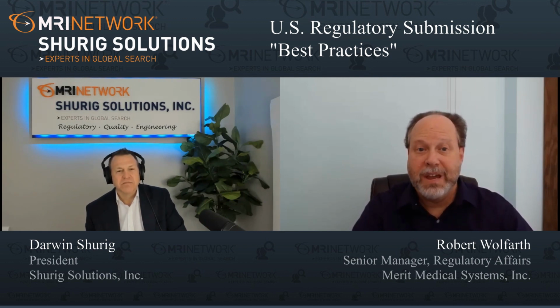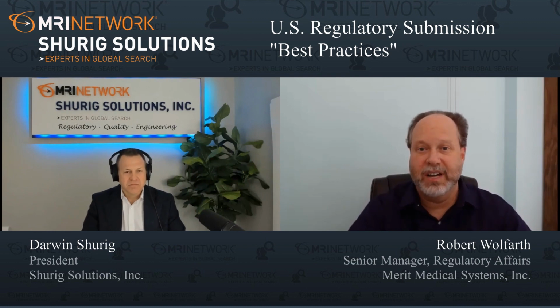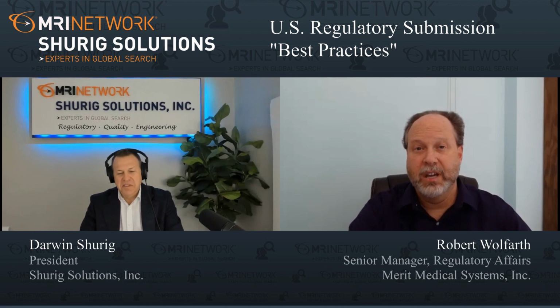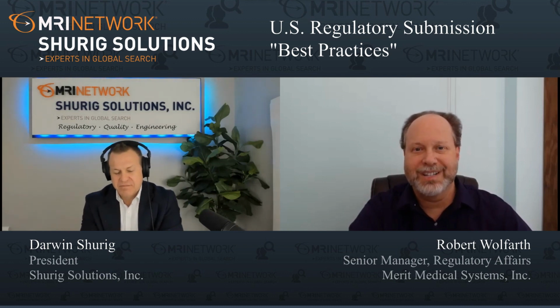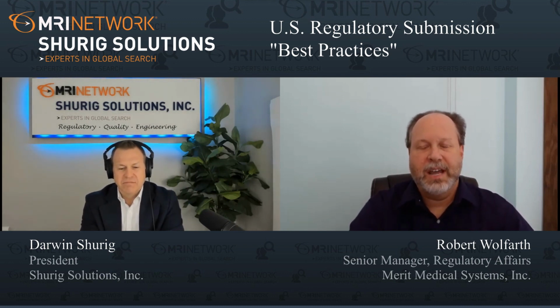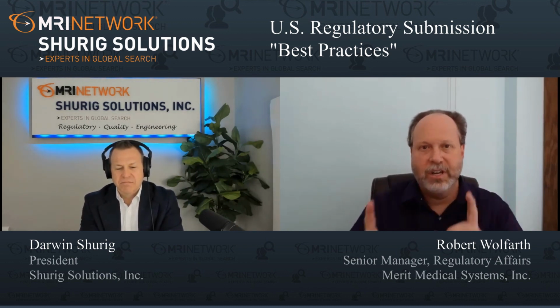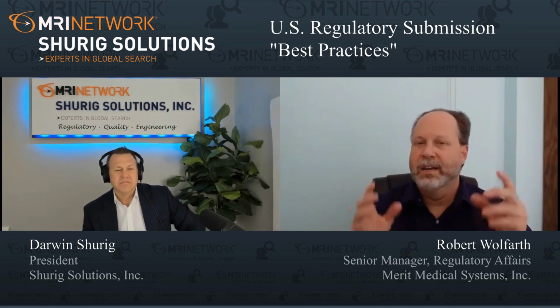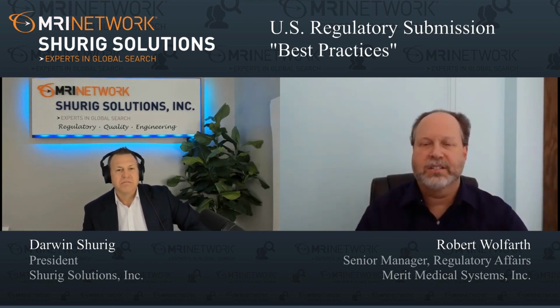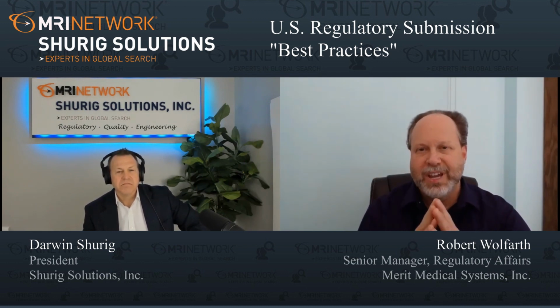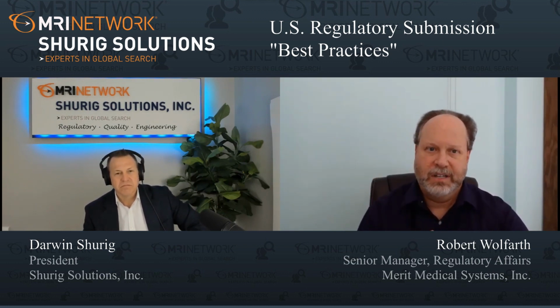Number 3, maybe the most important piece of advice in writing your 510K. That should get your attention. Yes. Tell a story. Don't just put all of the test reports together in a document and have each of your sections of the 510K say, this device passed all tests, see Appendix A for the report. Remember, the FDA knows nothing about your device.